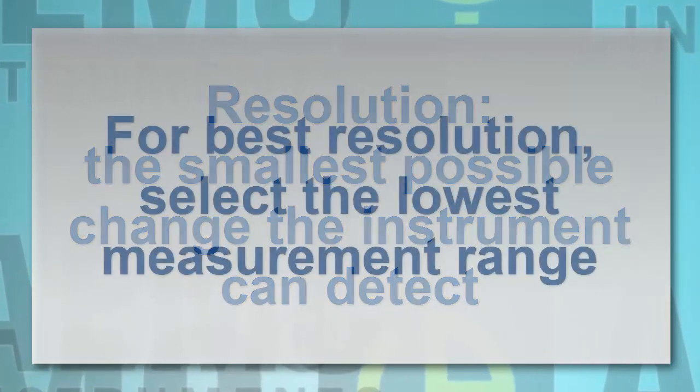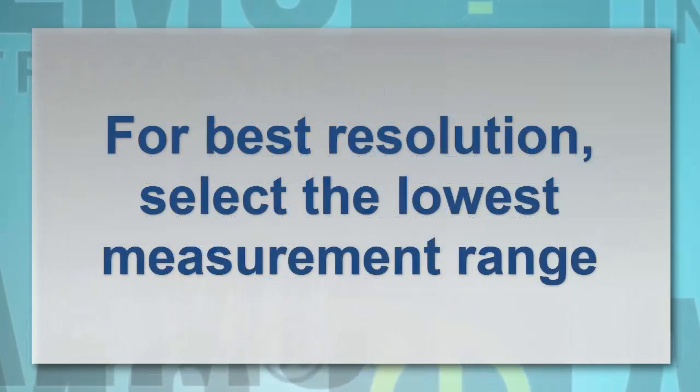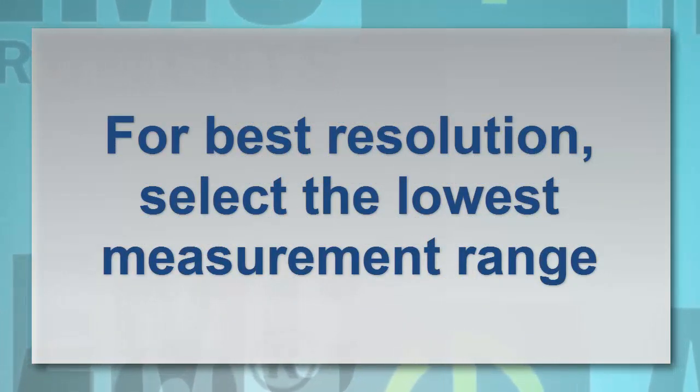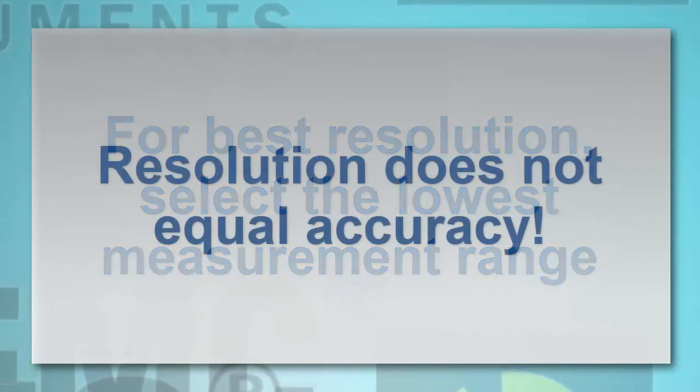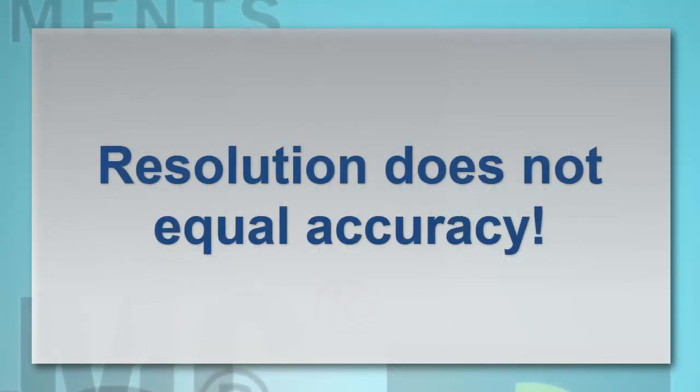And since resolution depends on the size of each unit, the smaller the better, the lowest possible measurement range should be selected when making high-resolution readings. However, these numbers say nothing about an instrument's accuracy. The one-thousand-count digital multimeter may have a measurement uncertainty much smaller than the ten-thousand-count model, and therefore produces more accurate readings. Although resolution is a critical factor in calculating uncertainty, it is not the sole factor.